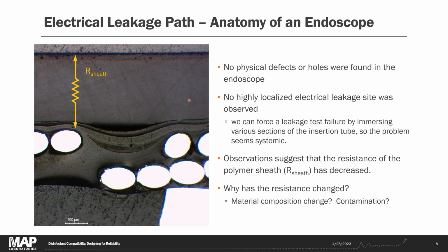In all of our testing, we were not able to discover any highly localized electrical leakage. It seemed like a systemic problem across the entire endoscope sheath. Our visual inspection similarly did not find any holes or tears or delaminated interfaces. So this suggests that the actual conductivity of the material has increased, or the resistance has decreased. We have to answer then, why do we think that happened? Is it contamination? Is it increased water in the material from humidity or soaking in water too long? And so to do that, we need to turn to another instrument.